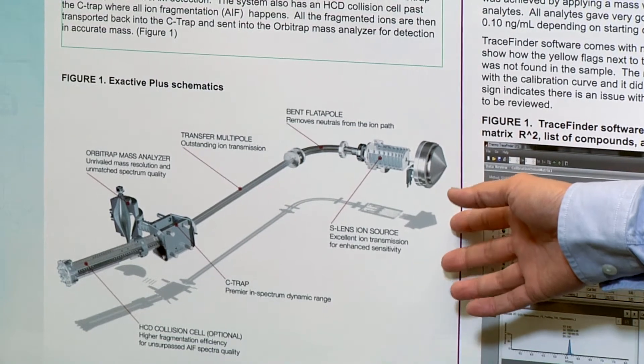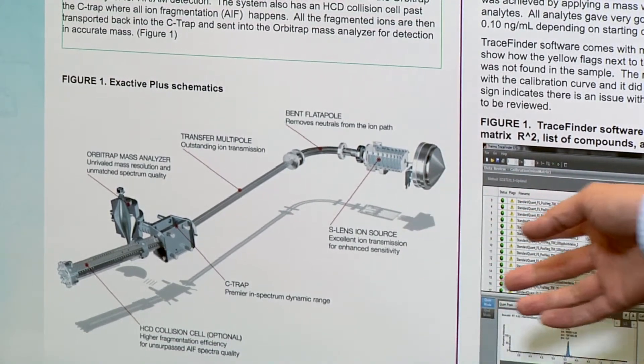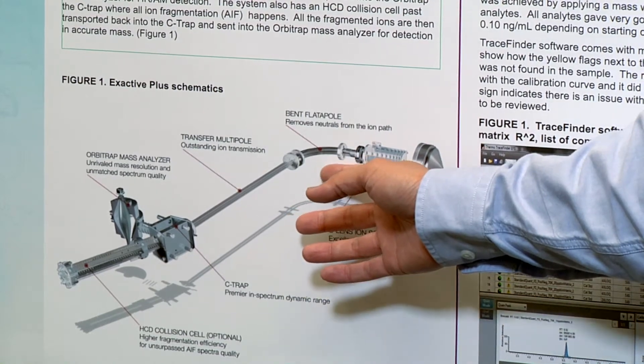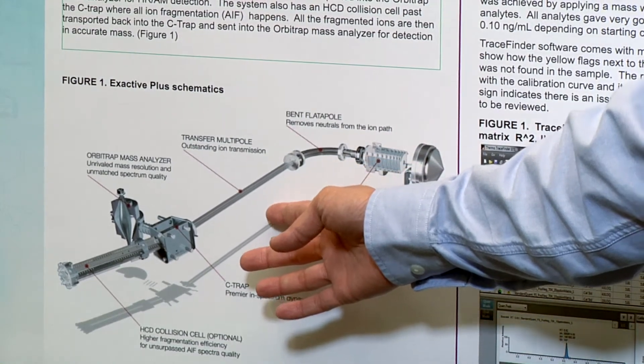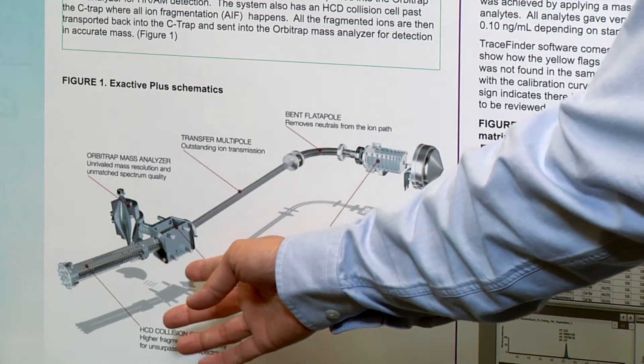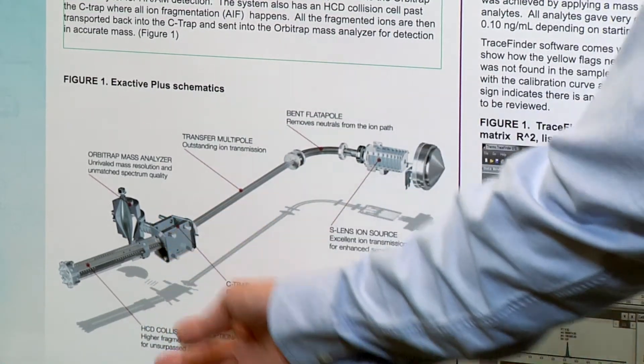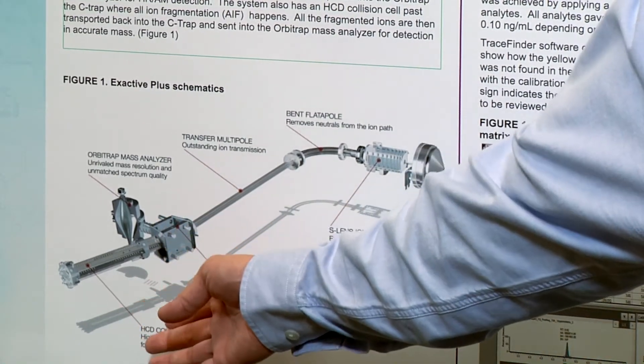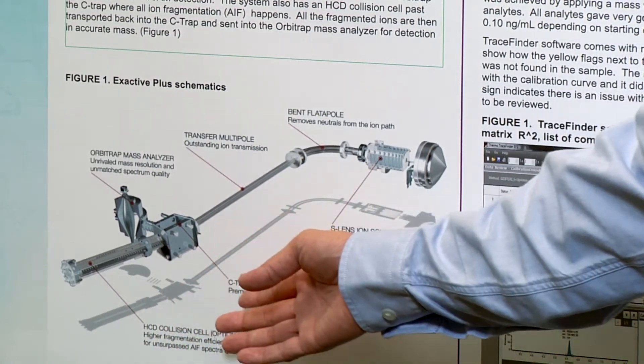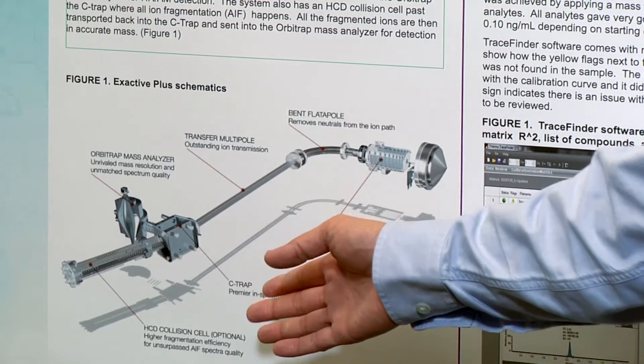From the diagram you can see the Exactive Plus, where we have the S lens, and then the ion goes through the bent flatapole, then through a transfer ion optic, and then into the C-trap, and then into the Orbitrap. We have an HCD cell behind the C-trap where all the ions are fragmented and then transferred back into the C-trap and into the Orbitrap.